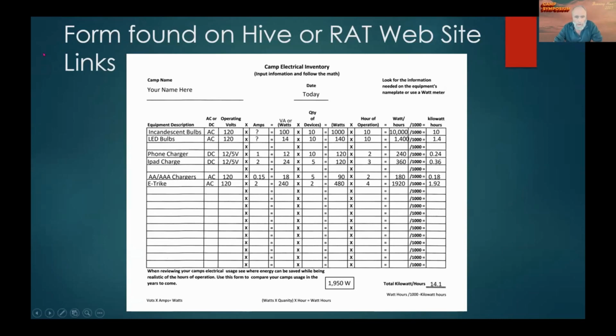Let's look at the first line. Here I have incandescent bulbs. I looked at the nameplate and it said AC for 120 volts. We would normally multiply that by the amps, but the nameplate doesn't have amps, it does have watts. On the bulb, it says 100 watts. We have 10 of these devices, so we multiply that together and end up with 1,000 watts.